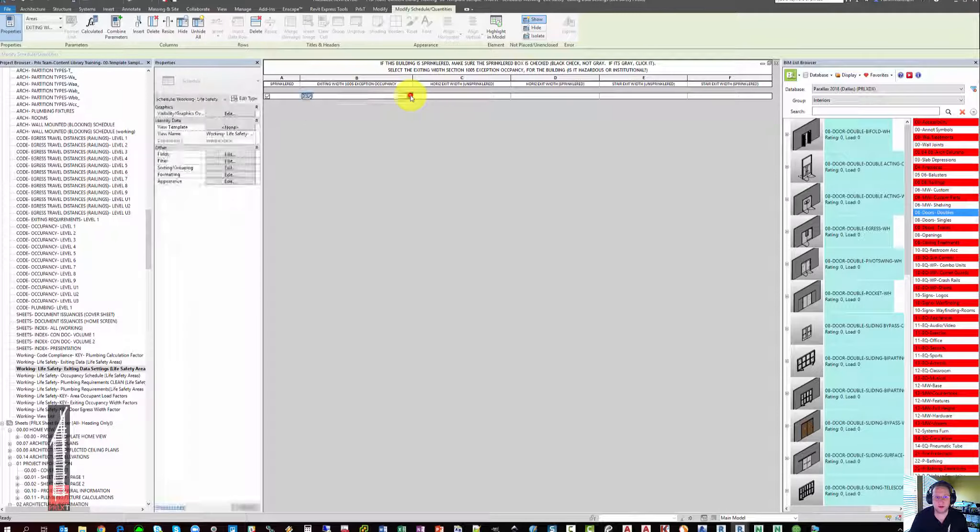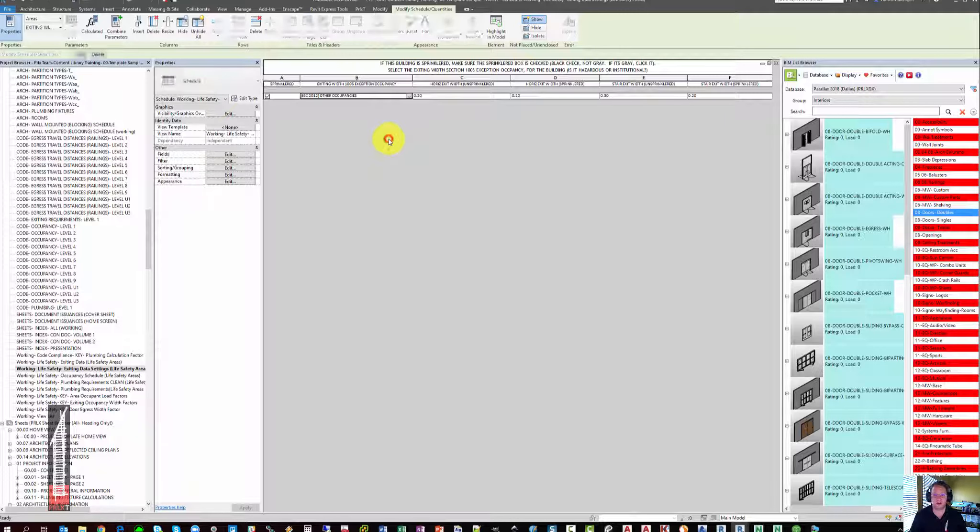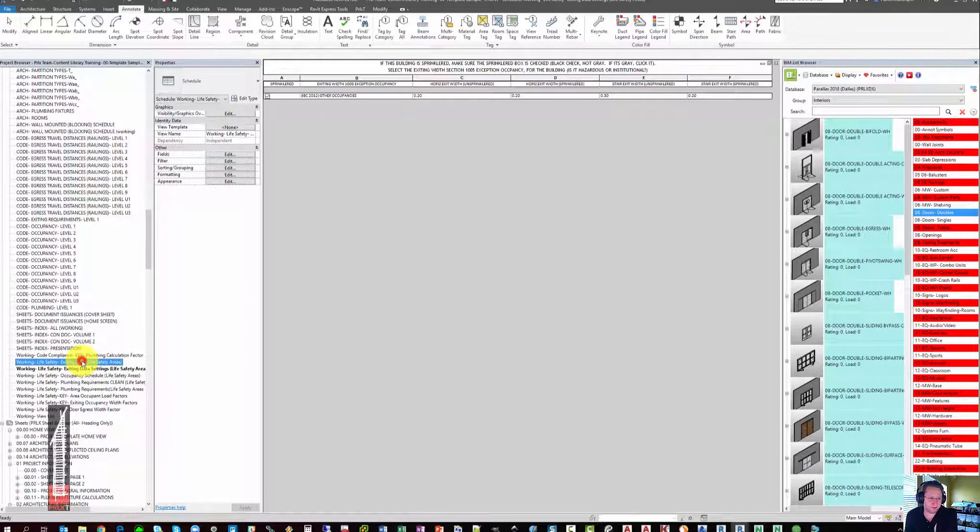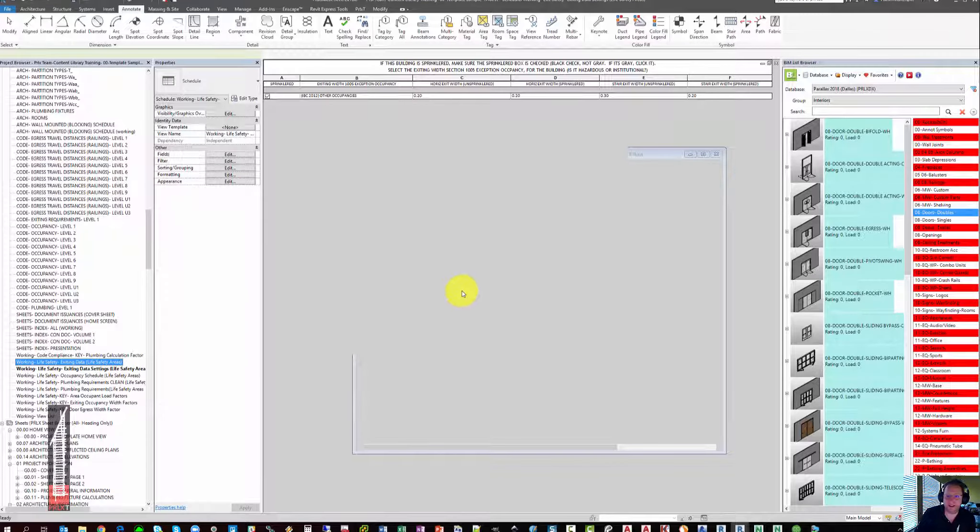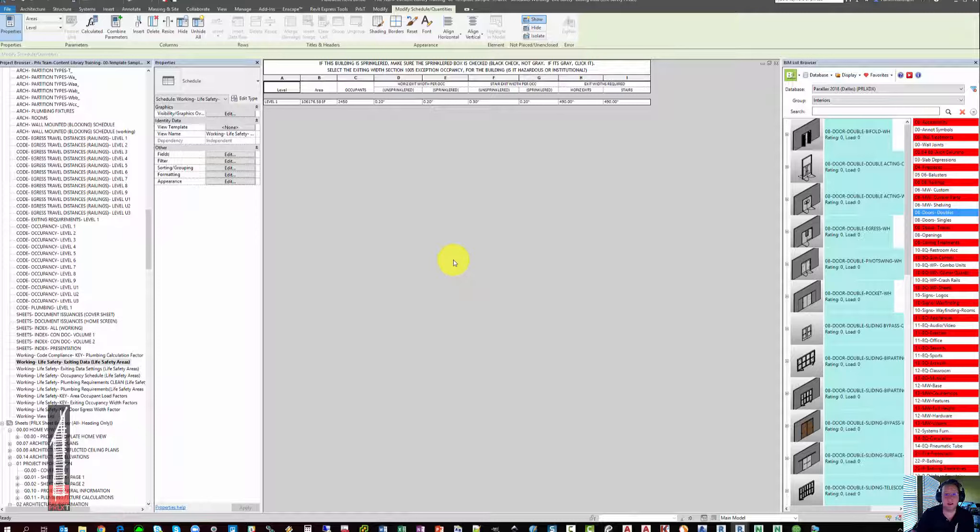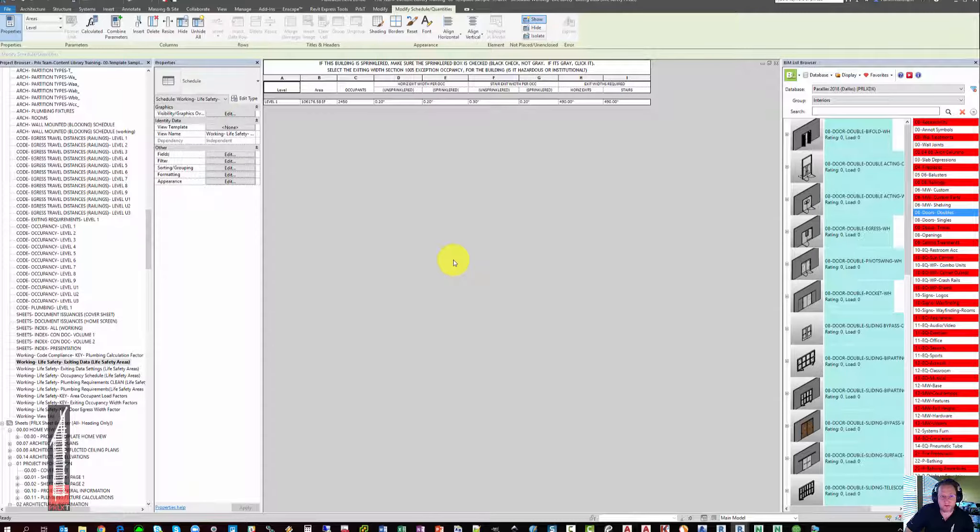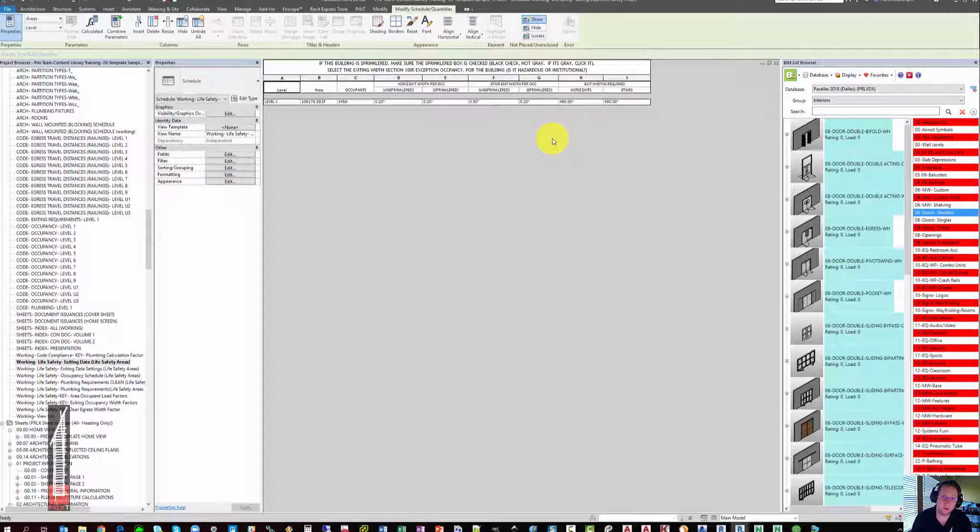is there the Exiting Width 1005 exception being hazardous or institutional occupancies, and we're going to say no, so we're going to pick Other. You'll notice that the moment we do that, it starts to give us all of our Exit Width requirements, which is unsprinklered and sprinklered versions, 0.2 and 0.3 inches. If we then go to our final schedule called Exiting Data, you'll see that it has calculated based on this make-believe model with 106,000 square feet. We essentially need 490 inches of Exiting Width. You can now compare this to your egress doors and see how you come out.